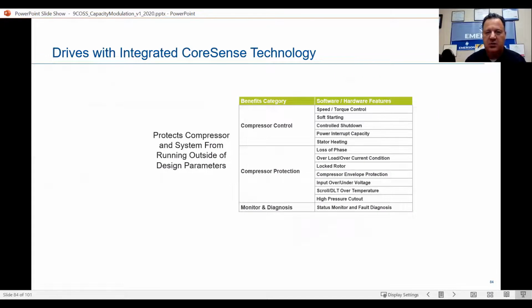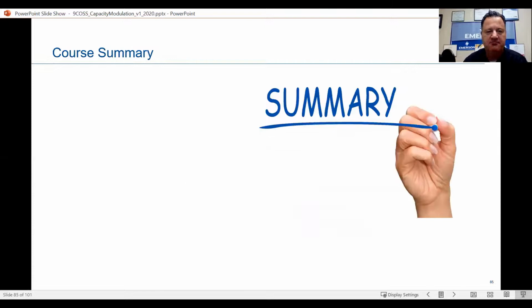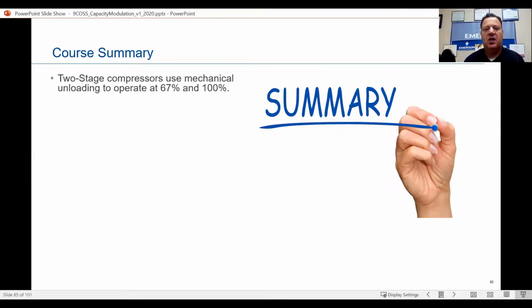Drives with integrated CoreSense technology. Of course, you can put CoreSense on there. The benefits: the compressor is controlled, compressor protection, the monitor diagnostic, protects compressor and system from running outside the designed parameters. In summary, 2-stage compressors use mechanical unloading to operate at 67% and 100%. First stage being 67% and 100%.